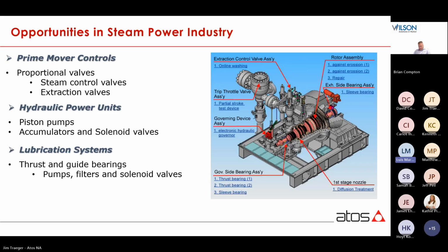As far as opportunities in the steam power industry, the prime mover controls have proportional valves that operate steam control valves and extraction valves. Again, there's also a hydraulic power unit with piston pumps, filters, accumulators, and solenoid valves. Also lubrication systems for thrust and guide bearings, with pumps, filters, and solenoid valves. Again, all these components are required to be serviced or replaced. Here's a picture of a steam turbine, indicating at the top the extraction control valve. Those are servo hydraulic driven. And there are guide bearings on these units that require special lubrication. Next slide.